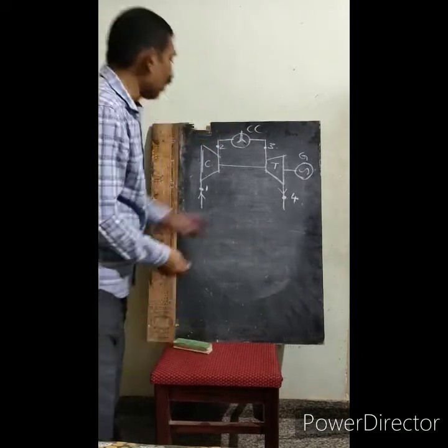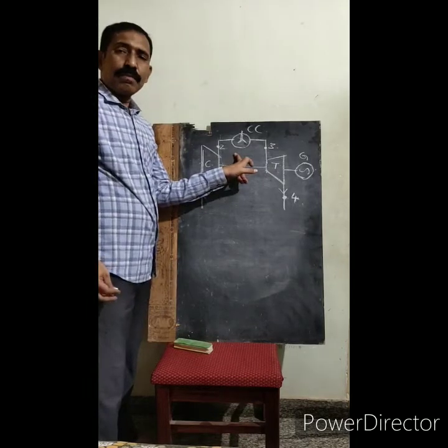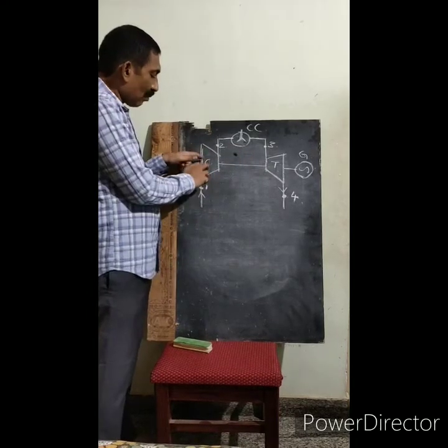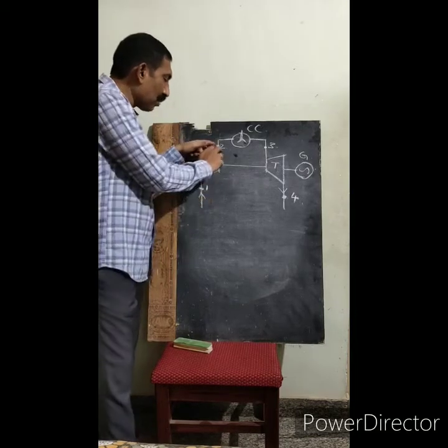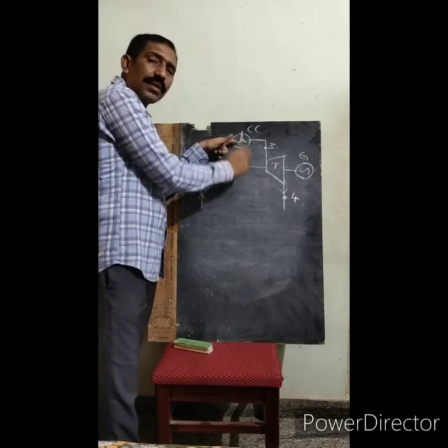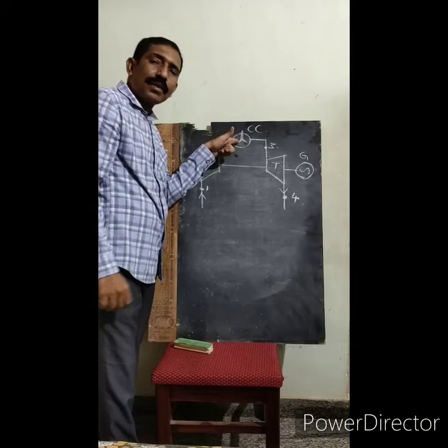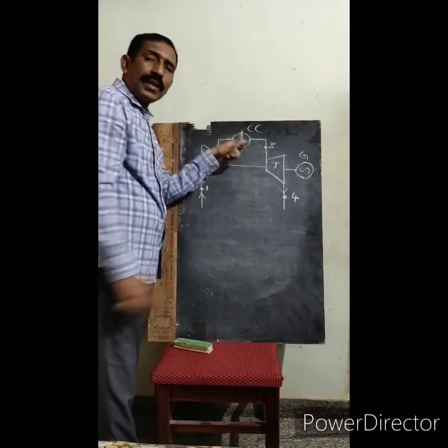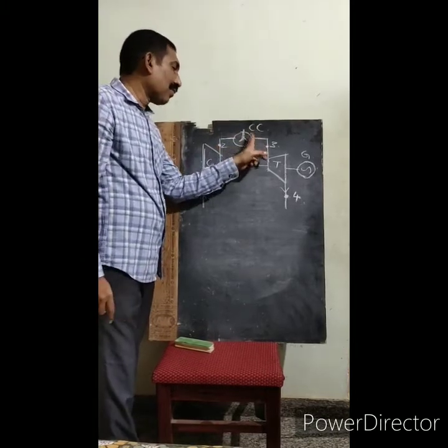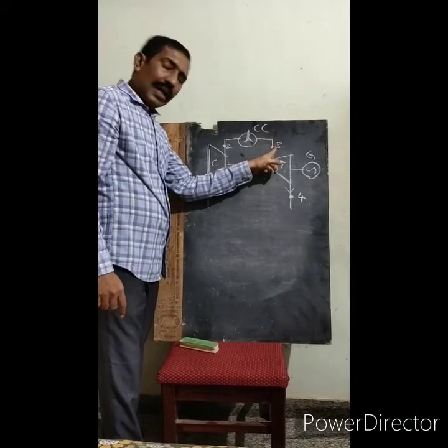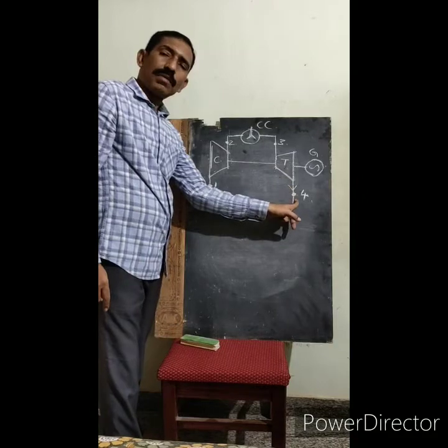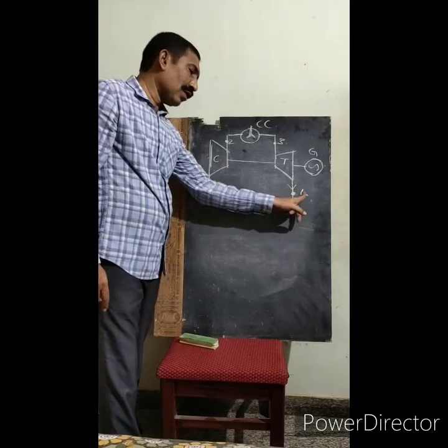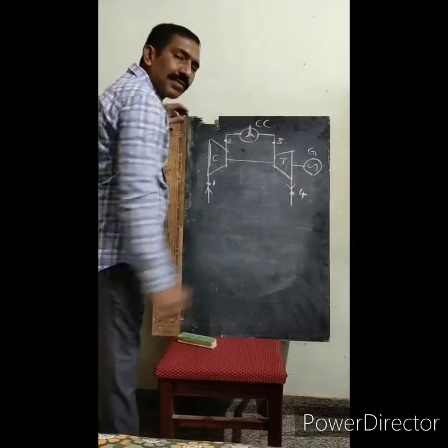This is the simple Brayton cycle. Here the air is compressed in the compressor from low pressure to high pressure, and then it goes to the combustion chamber where the fuel is added and heat is supplied, so that its temperature is increased at constant pressure. After combustion, the gases at high pressure and temperature go to the turbine, where they get expanded to the atmospheric pressure P4. After that they are left to the atmosphere.